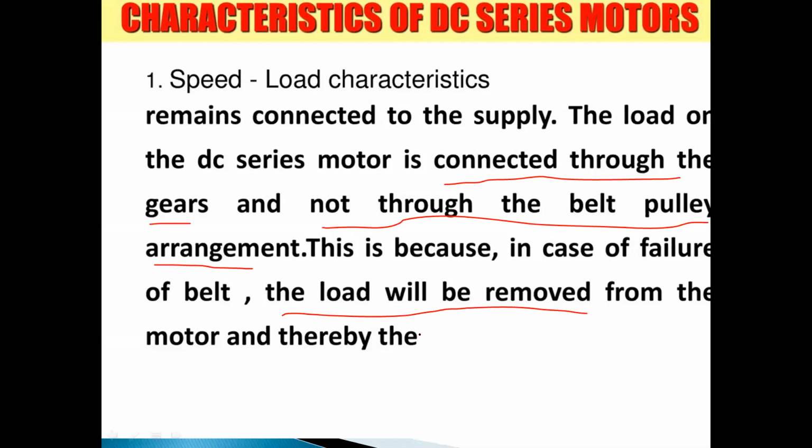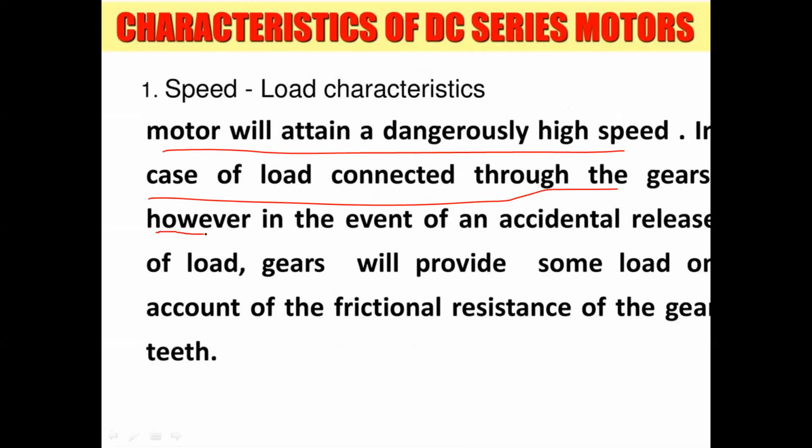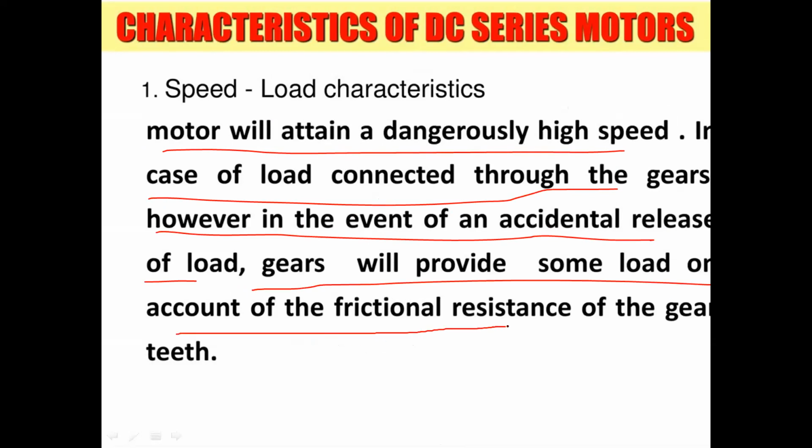The load would be removed from the motor and thereby disconnected. The series motor must be connected to the gear system. Very important. The motor will attain a dangerously high speed at no load. In case the load is connected through gears and is accidentally released, the gear will provide some load on account of the frictional resistance of the gear teeth. So the motor is connected through a gear system. Between the motor and load, we provide a gear system, not pulleys and belts.